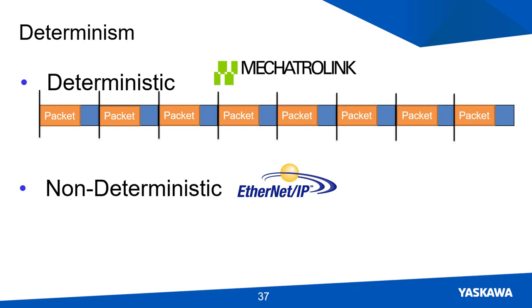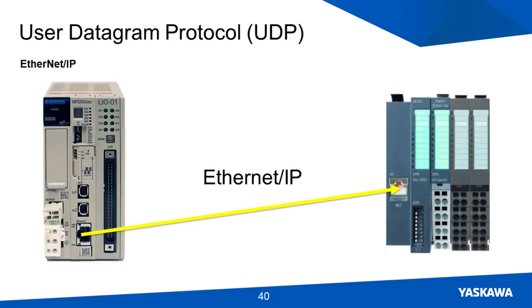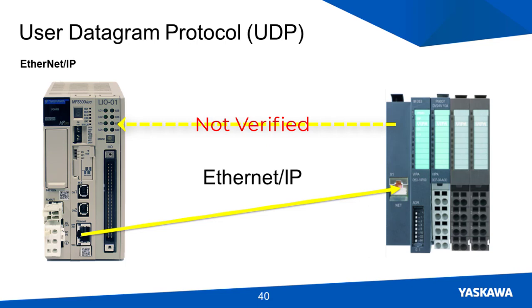Compared to non-deterministic networks where transmitted data occurs within a time band, but the packets are not transmitted and received at a constant rate. In the case of Ethernet IP, since it uses UDP, user datagram protocol, to transfer information, the master cannot verify whether the slave has received the information or not. So there is potential for the slave to miss packets of information.